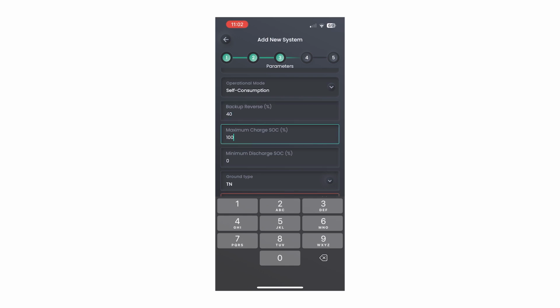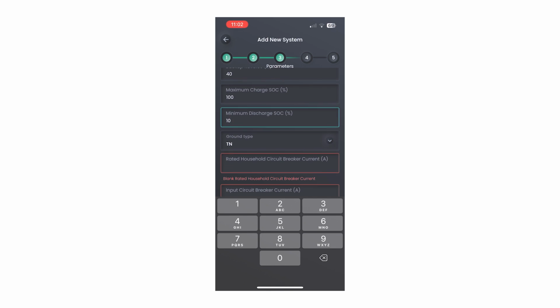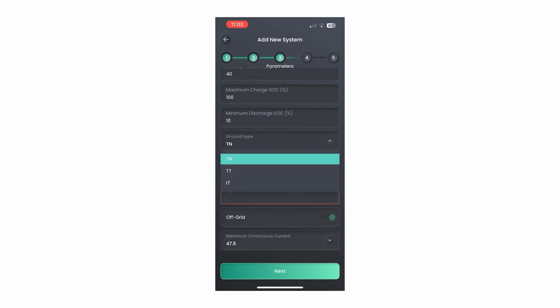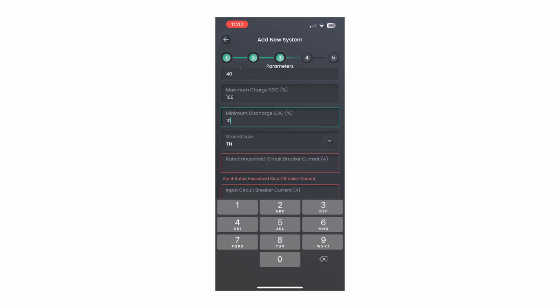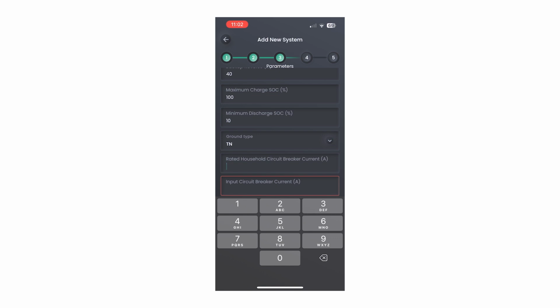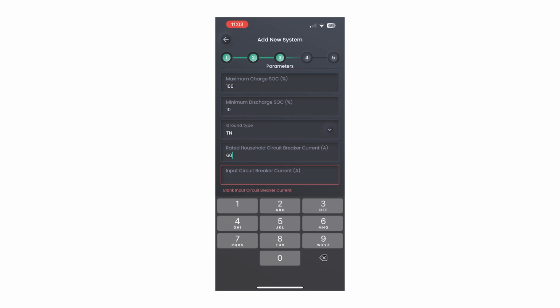Maximum state of charge is going to be 100%. Minimum discharge state of charge, we could put 10% or 0%, depending on what we want. Ground type, don't worry about that, TN is fine. Rated household, I'm going to put 60 amps in here, and input circuit breaker current, 48 amps.